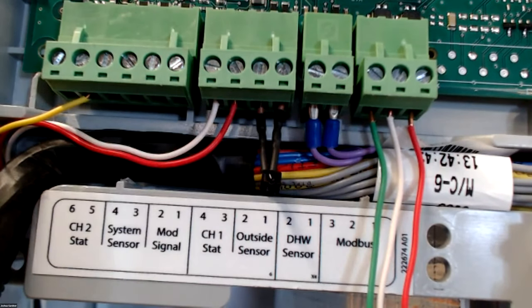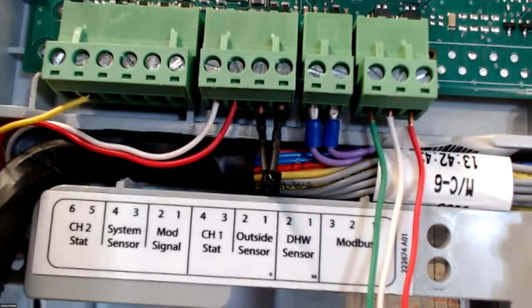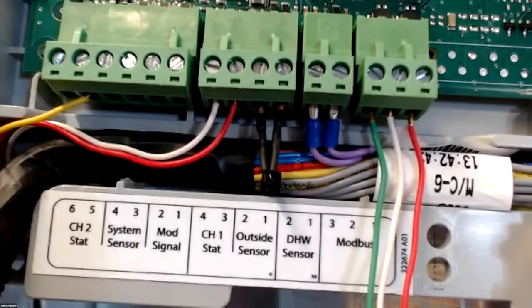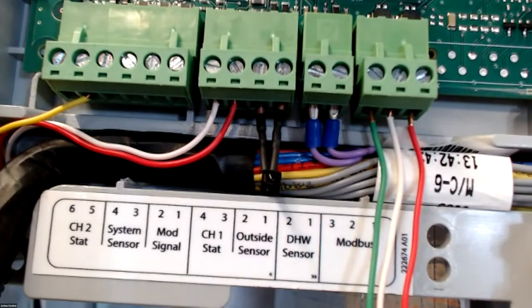Also, making sure that it's far enough away from bath fan exhausts, because that can throw it off. Make sure it's away from dryer vents as well. And then make sure it's away from the exhaust of the boiler. That's probably the most common problem I see, is because everything is just in that area. You run your intake out, you run your exhaust out, and your outdoor sensor usually goes right there because that's the easy place to put it. That exhaust will throw this thing off 20 degrees easy. I've seen it, saw it the other day. So make sure that outdoor sensor is placed somewhere appropriately so you can read that outdoor temperature.